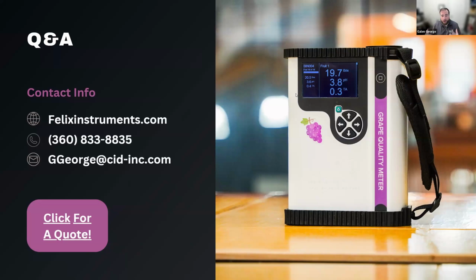Then there's what we call the offset or bias calibration. We typically recommend you do it at the beginning of every season, before you start using the instrument for the duration of the season. It involves performing some scans of the fruit, and then you take that same fruit and analyze it with the refractometer, with a laboratory, to get comparative results. That allows you to adjust the bias and predictions on the device itself. Sometimes a bias arises, but that is mostly eliminated through us integrating multiple different seasons in the model itself. Since we've integrated all those seasons, it shouldn't be a very big issue.